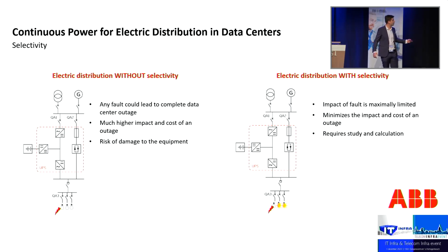And instead of losing just one branch, just one supply, typically in a data center this would be for the group of racks or maybe for one rack, depending on where downstream in the distribution the fault is, I would lose the whole line. I would lose the whole system block. In case I do have selectivity, and you see over here, I would lose just this one small branch, and I would have the whole rest of the system redundant and still available. So here is actually where we need to study and understand how we can have full selectivity and again improve the reliability of the data center.